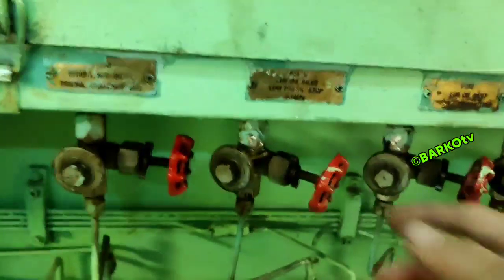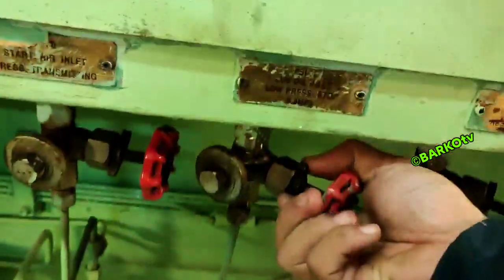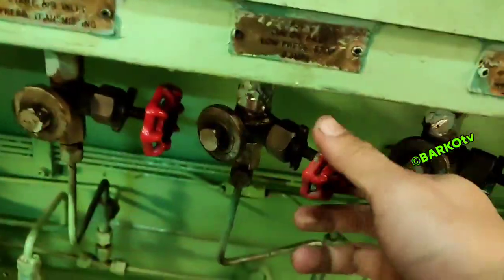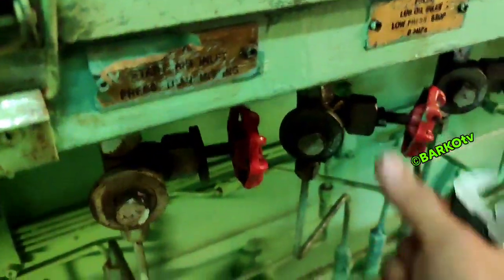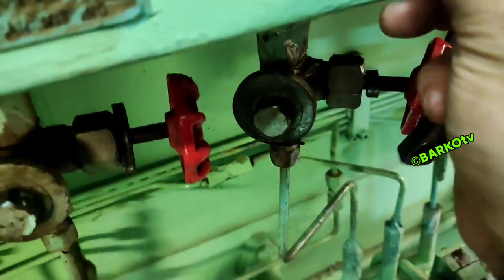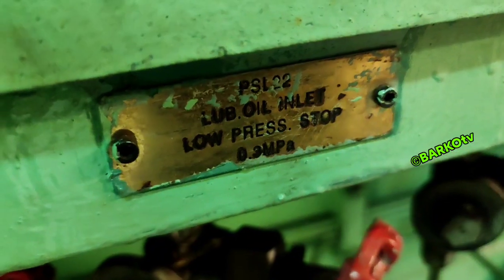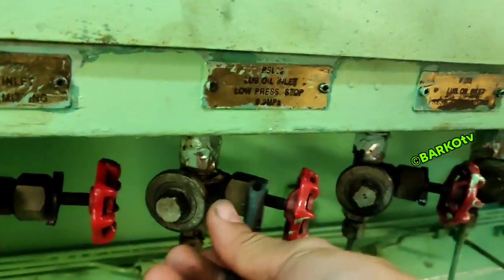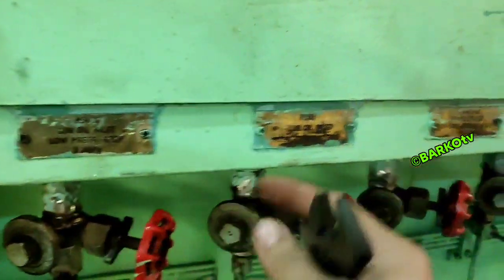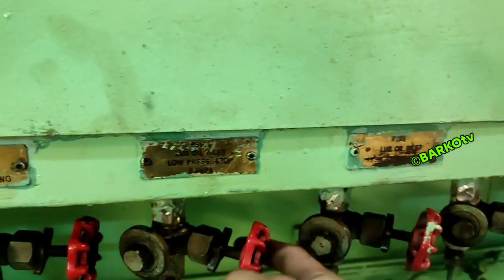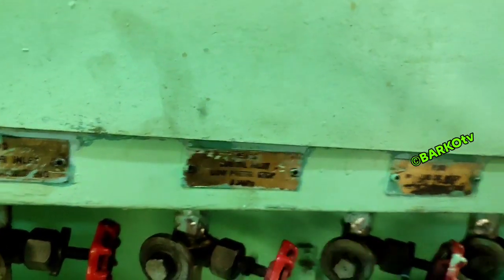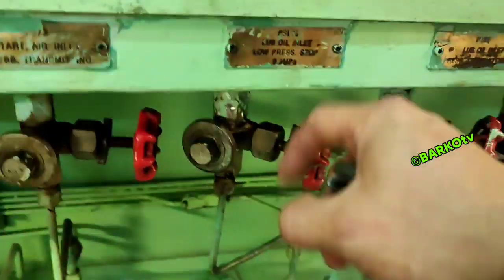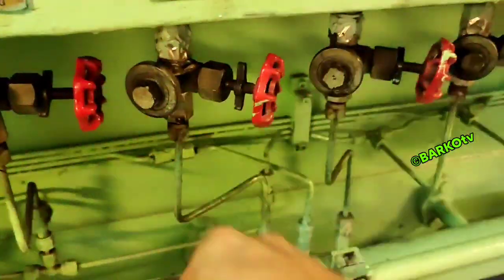First, lube oil shutdown. There is a label, lube oil low pressure stop. Okay, close this three-way valve, loosen the securing nut, and then close the valve. This is how we simulate the low pressure stop or shutdown. This at the right side is the transmitter, but here is the pressure switch which activates the low pressure shutdown.